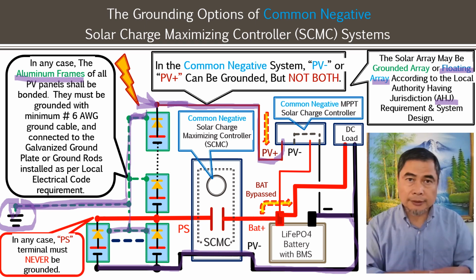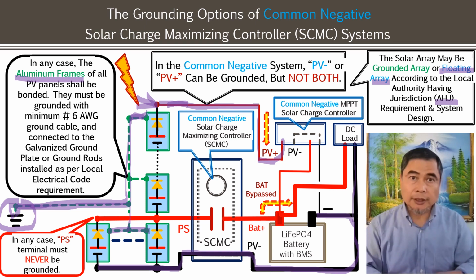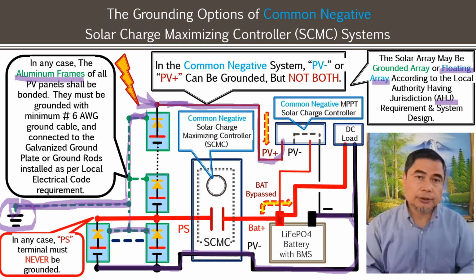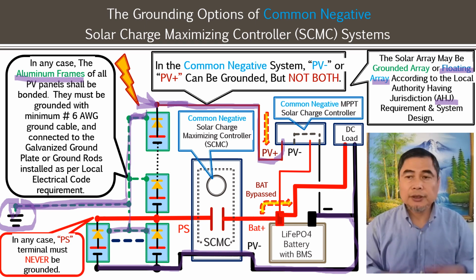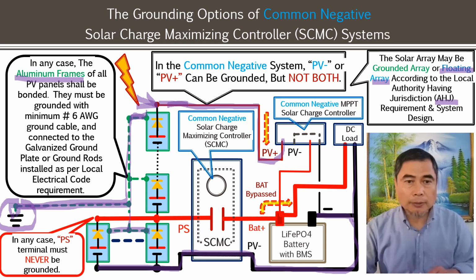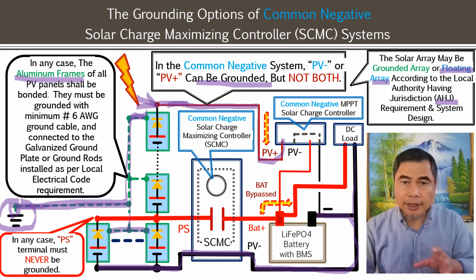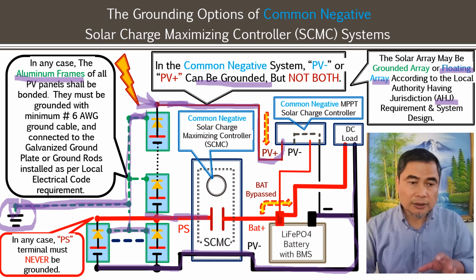The grounding design, based on local electrical code, should be deep enough, with a galvanized metal plate or some special construction, depending on the soil condition. Make sure that the ground is approved based on the local building code. So that frame has to be grounded, but you have an option here: in a common negative system, PV negative or PV positive could be grounded, but not both. You just do one. But in any case, as we mentioned, the PS line, the split wire line, must never be grounded. So that's the option you can have for a common negative design.